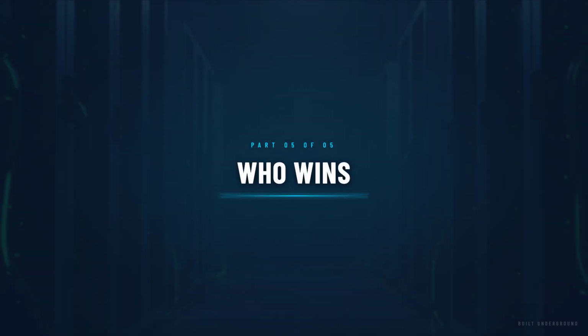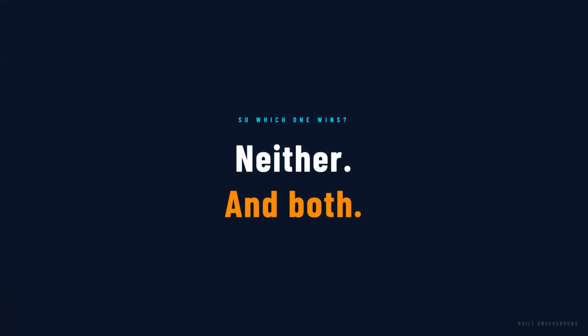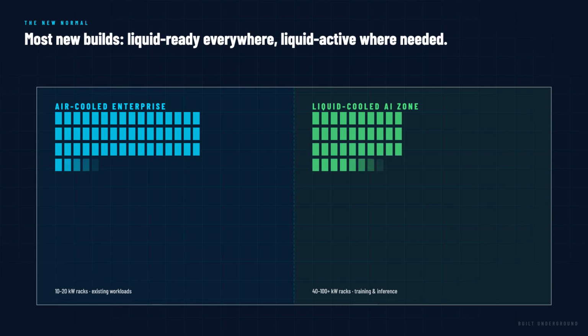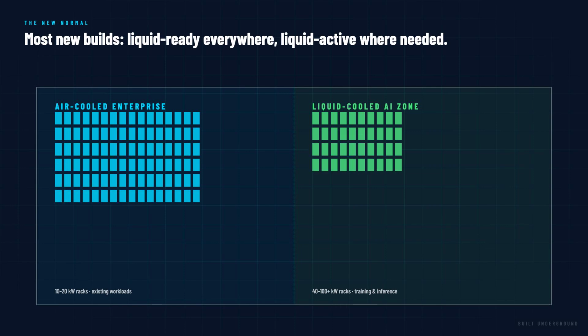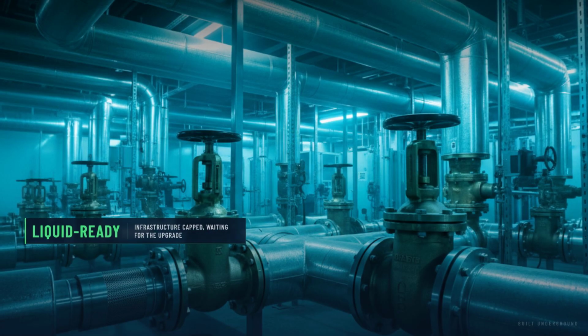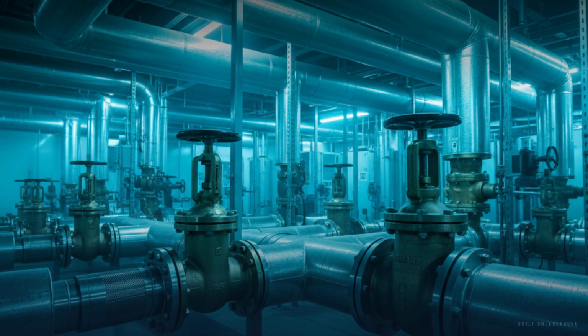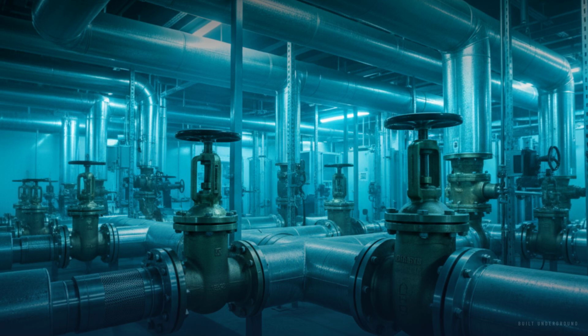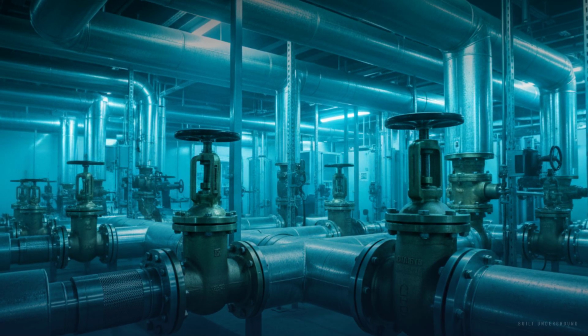Neither, and both. The data center industry is not replacing air cooling with liquid cooling, it is layering liquid cooling on top of air cooling where the density demands it. Most new hyperscale facilities being designed today are liquid cooling ready. The pipework, manifolds, and coolant distribution infrastructure is installed during construction, even if the initial tenants are running standard air cooled workloads. When those tenants upgrade to higher density hardware, or when AI workloads move in, the liquid cooling infrastructure is already there. For enterprise and co-location facilities running traditional workloads, air cooling with modern containment and free cooling remains the most cost-effective solution and will be for years.